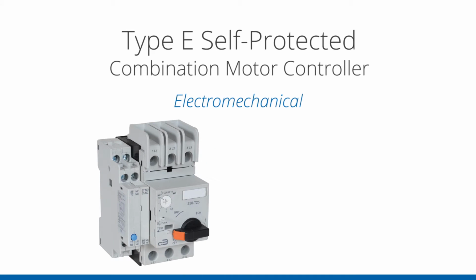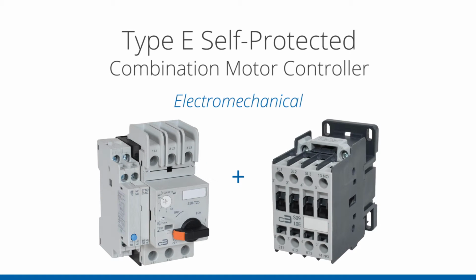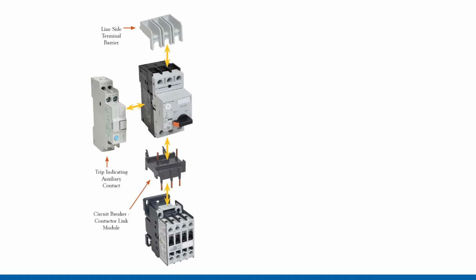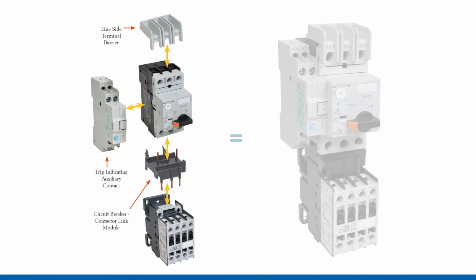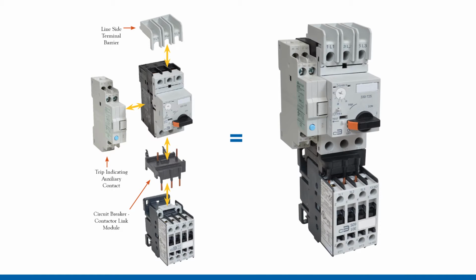Similarly, an electromechanical Type E self-protected combination motor controller will include a contactor for remote operation. In this case, the motor protection circuit breaker, the trip indicating auxiliary, the line side terminal barrier, and the specific contactor are all tested together to provide the appropriate Type E rating, meaning that you have to use the listed combination of the devices to achieve the Type E rating. You can't just mix and match at will, but it is specifically based on how the product was tested.